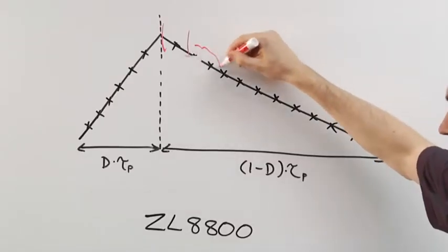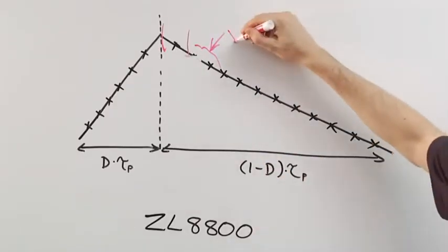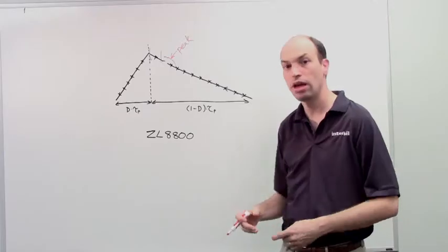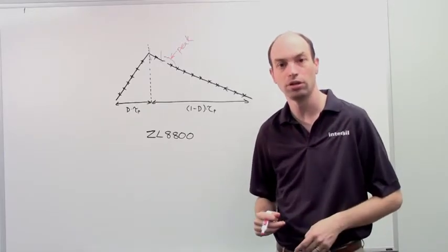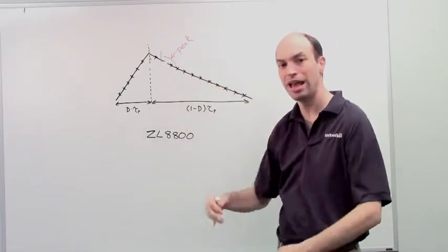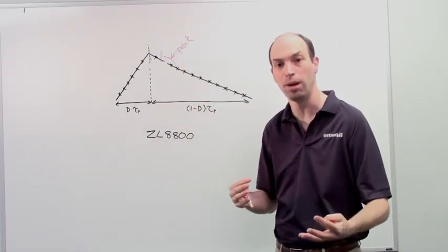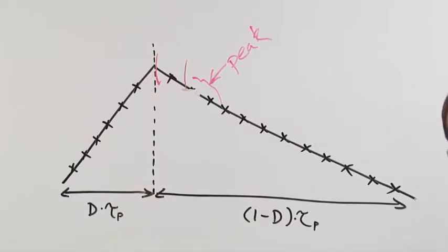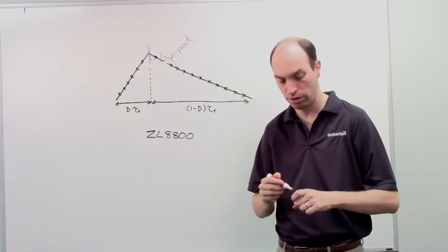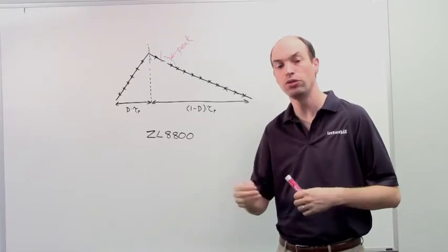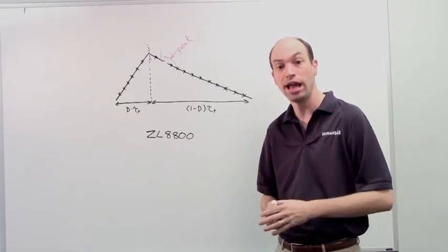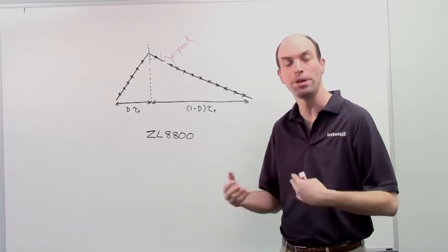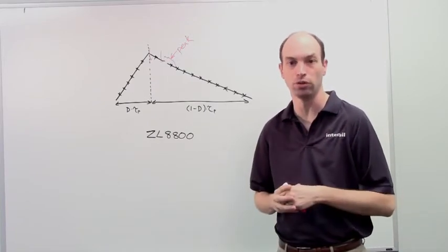Now, the first few readings are probably what's going to be tripping your peak overcurrent protection. This is a cycle-by-cycle protection, so every cycle is constantly monitoring it and comparing it to the peak threshold that's set up. All the other points, including those, are continuously sampled and averaged together. That way you also get an average overcurrent fault response. So for an overcurrent event, you get two settings, peak and average. And the same thing applies for undercurrent. There's also a peak undercurrent and an average undercurrent fault.